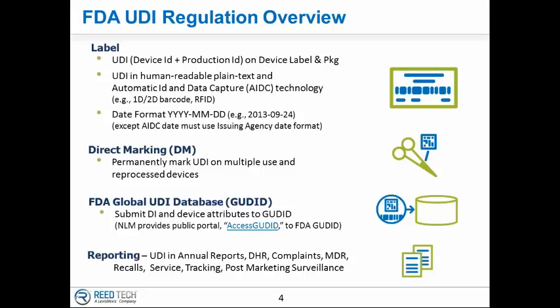Michelle asks, can you explain what the published date is in the UDI database? Yeah, well, that's a really good question, and there's a lot of questions about it. This is a date that does a couple things. One, it's the day that satisfies your responsibility for the device to the FDA. Secondly, it marks the transition from unpublished to what is referred to as the life cycle of a data record. You could submit a data record today and have the published date 2 weeks in the future.